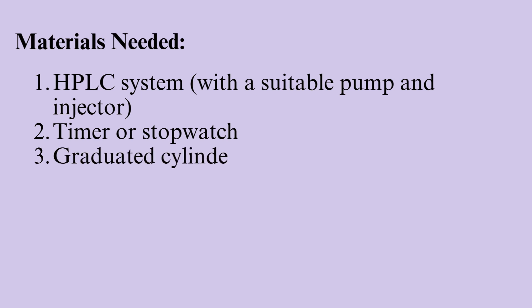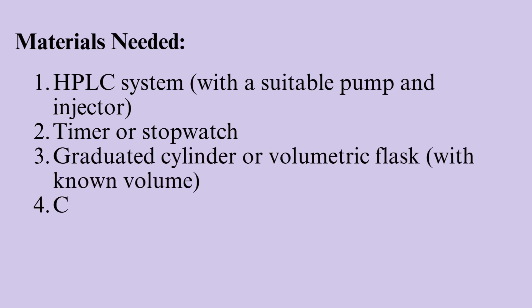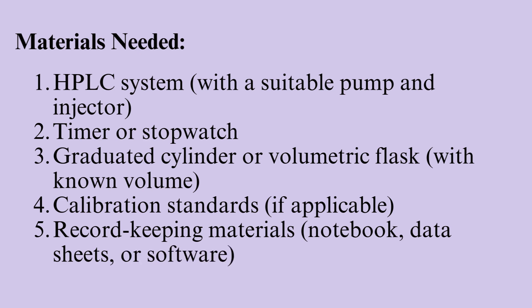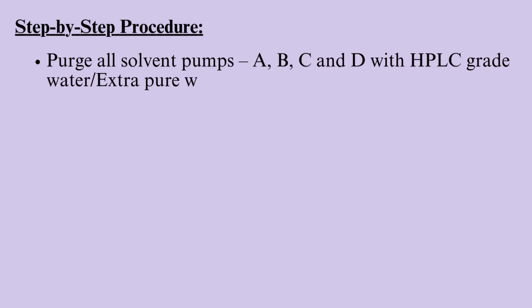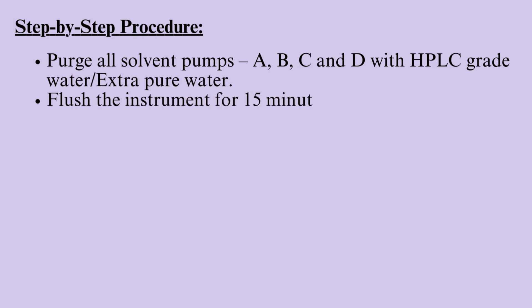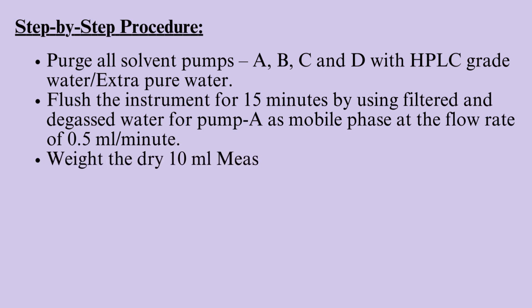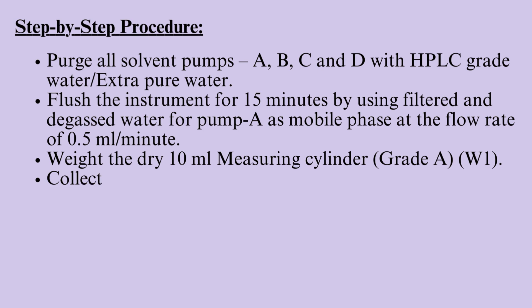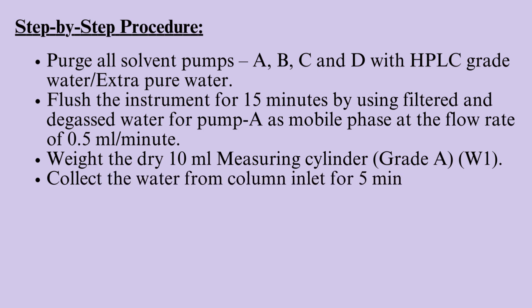Flow rate accuracy — materials needed: HPLC system with a suitable pump and injector, timer or stopwatch, graduated cylinder or volumetric flask with known volume, calibration standards if applicable, and record keeping materials such as notebook, data sheets, or software. Step-by-step procedure: Purge all solvent pumps A, B, C, and D with HPLC grade water. Flush the instrument for 15 minutes using filtered and degassed water for pump A as mobile phase at a flow rate of 0.5 milliliters per minute. Weigh the dry 10 milliliters measuring cylinder, grade A (W1). Collect the water from the column inlet for 5 minutes.